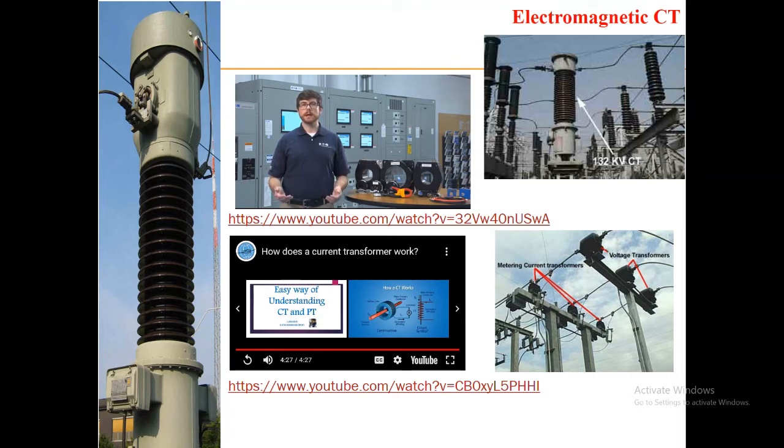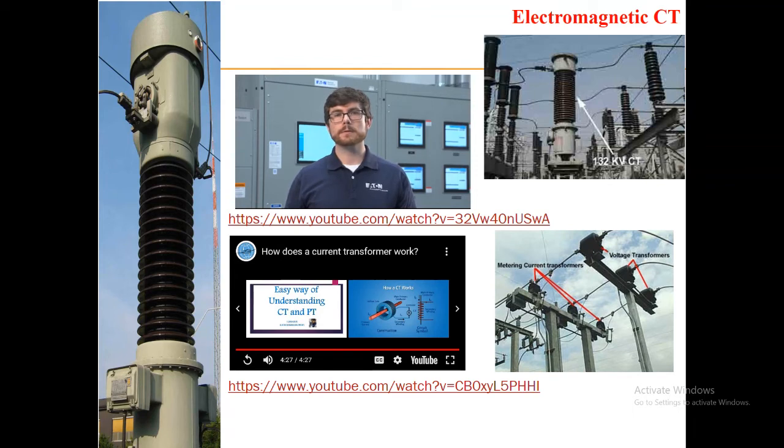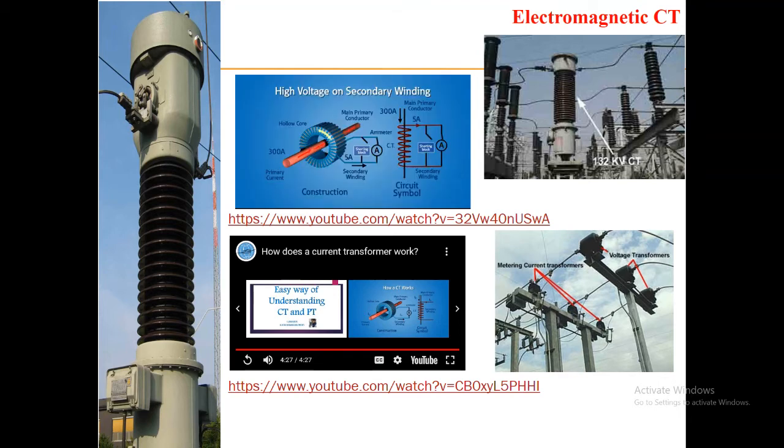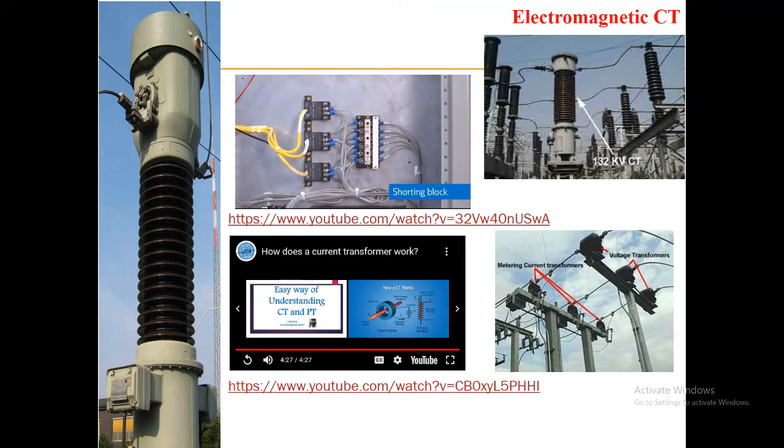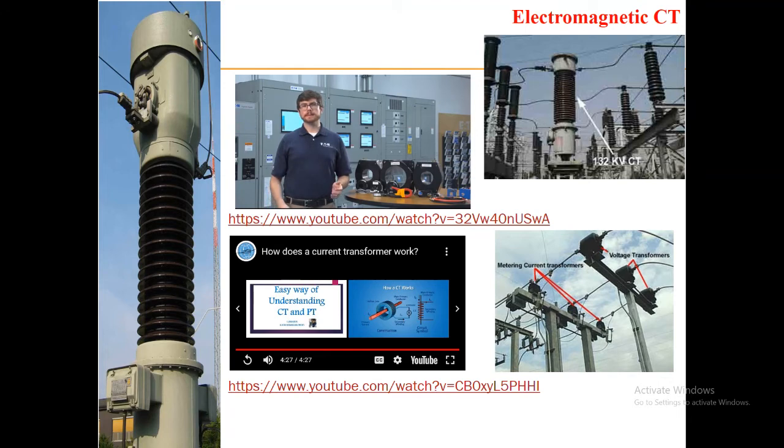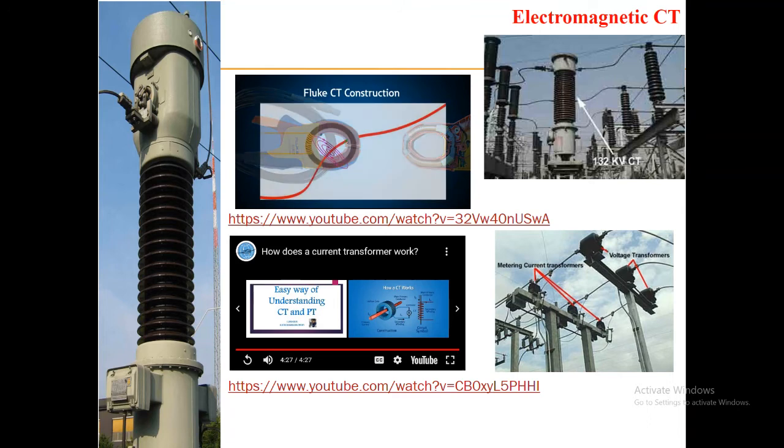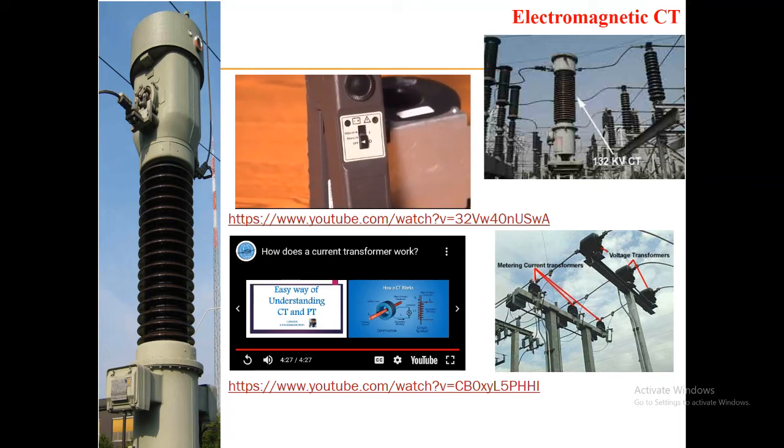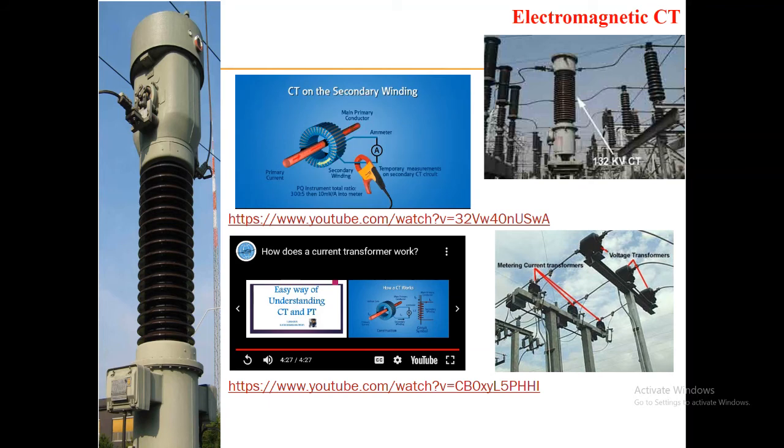Most CTs have a 5 amp output, but others have 1 amp, so when interfacing with a meter or circuit breaker, the correct multiplier must be used that will convert the 5 amp or 1 amp to the actual measured value. But even though the current steps down 300 amps to 5 amps, the voltage will step up on the secondary winding. An open circuit on the CT secondary winding can have dangerously high voltage of thousands of volts. When CTs aren't in use, they should always have their secondary winding shorted for safety by using a shorting block or a temporary jumper.